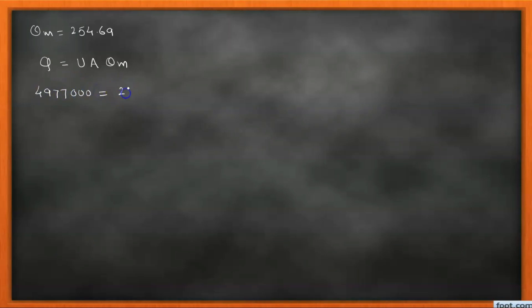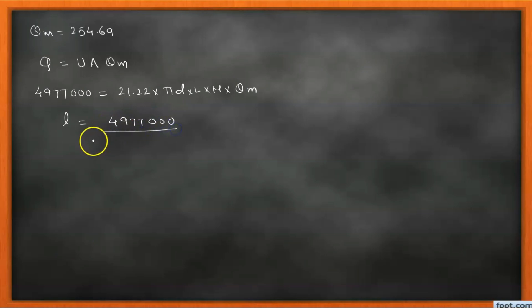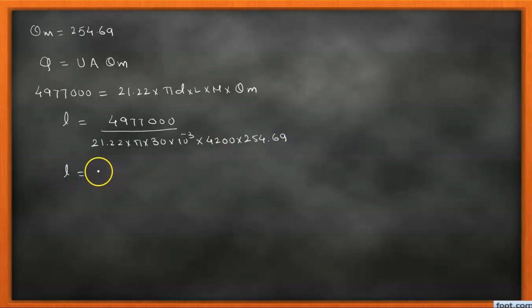Finally, using Q = U × A × θ_m where A = π × D × L × N, we solve for L: L = Q / (U × π × D × N × θ_m) = 4,977,000 / (21.22 × π × 30 × 10⁻³ × 4200 × 254.69) = 2.31 m. So the required tube length is 2.31 meters. Thank you for watching this video.